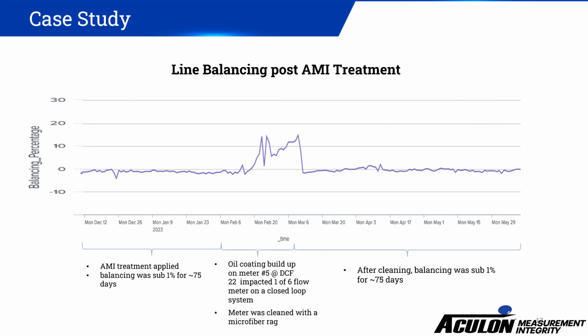During the entirety of this case study, we ran both our AI and line balancing systems in the background. As you can see on the graph depicted, we applied the AMI treatment on December 12th. And after it was applied to the 6 meters, we maintained a sub 1% balance for about 75 days. Then in the middle to beginning of February, we started to see a line balance creep. We continued to watch it and see if we could note or detect which meter was affected.